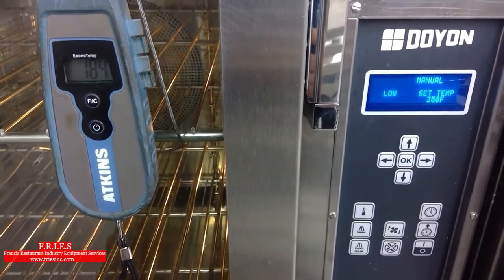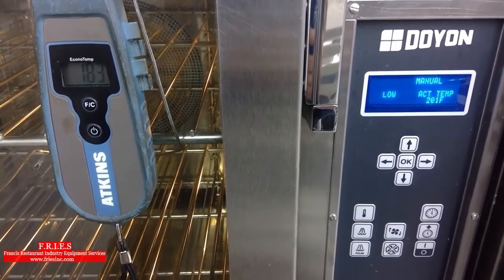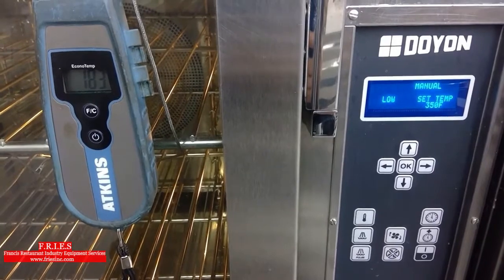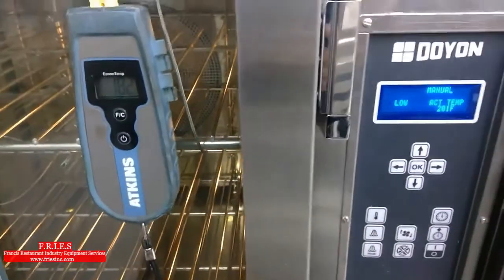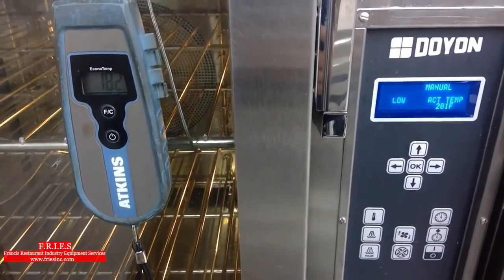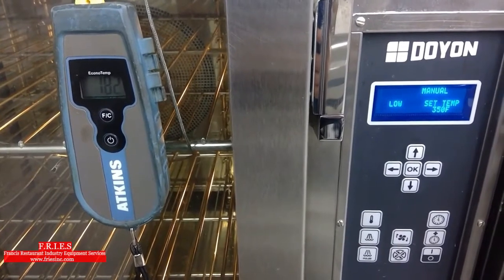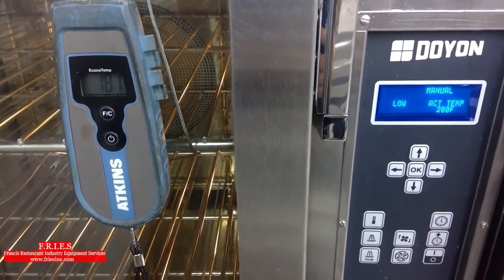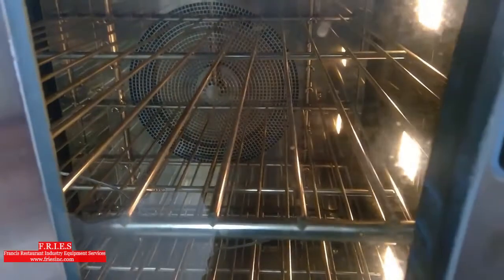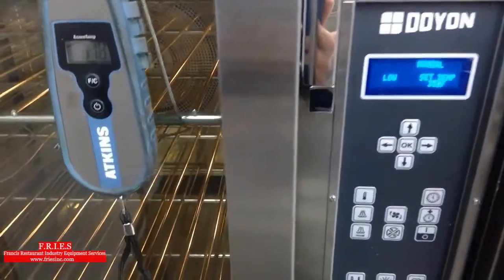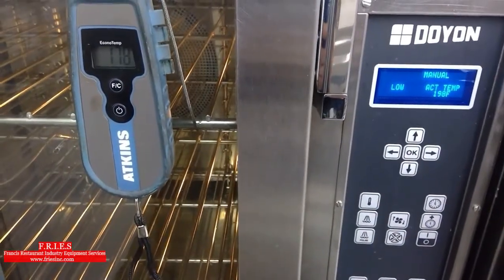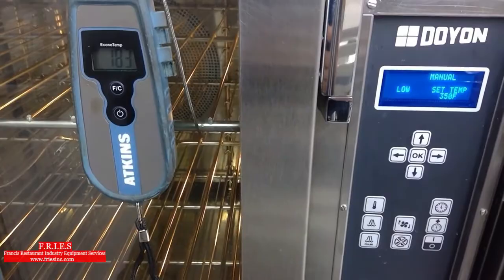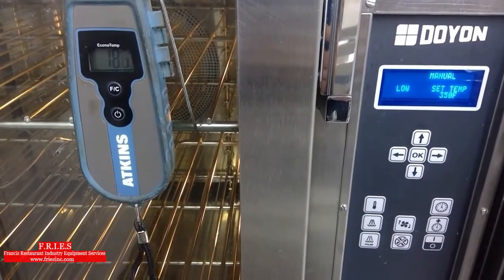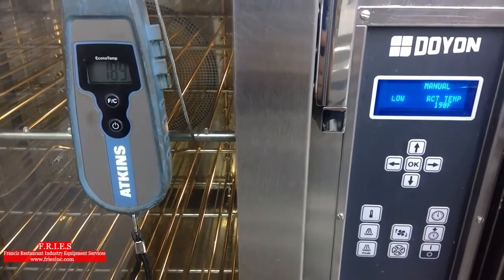The reason for that is we want even heat distribution, so we don't want just the right hand side of the oven, all that product, to get the heat. It has to go to the other side. So you'll actually see this happen in combi ovens as well. It's pretty important in the baking equipment. It just makes for even cooking, even heating. Alright, so blower just turned back on, burner's back on, temperature's going up. So far so good.